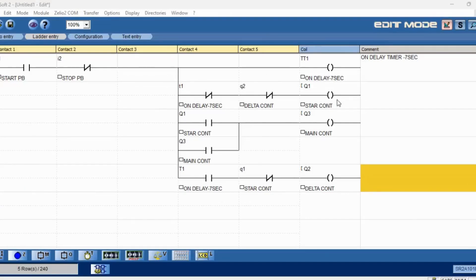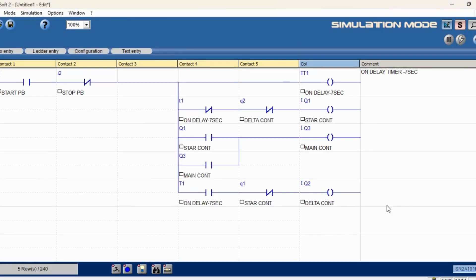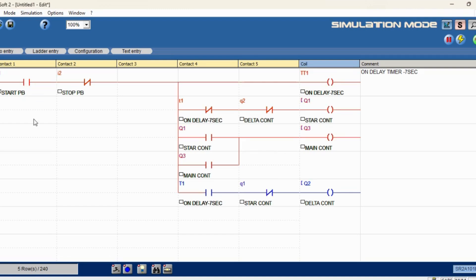We have made our ladder logic as per the star and delta operation. This is the edit mode. We will click on simulation mode — now it is in simulation mode. PLC is not yet started to run, so we will activate to run. You can see PLC is running. We will give the start command — motor has to start, star and delta motor has to start.